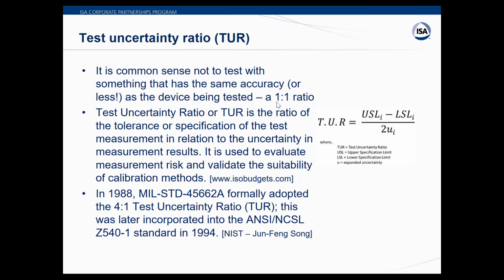So there's some things you can do. If you know that you have a poor quality measurement going on, you can do repeatability, or you can check it more often. You can send your standard off more often than it normally would be in order to be assured that you're getting somewhere close to true. But once you get to this 4-to-1 window, your confidence can go way up, and it's just good practice, let's leave it at that.